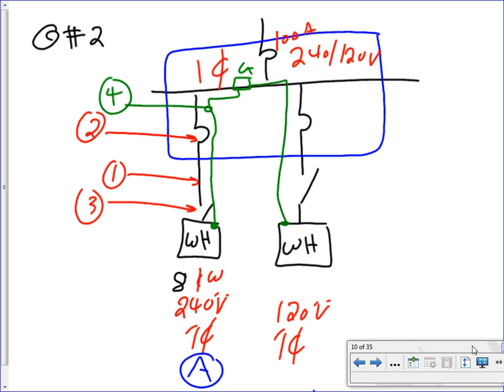So the same thing, guys. You have a feeder that powers water heaters, and there's 2 of them, and you, Adam, are required to do how many on the test? 1, because it repeats itself. The reason why I put 2 is 1 for practice. So here's 2 of them. I have 8 kW, and this one's supposed to be 3 kW.